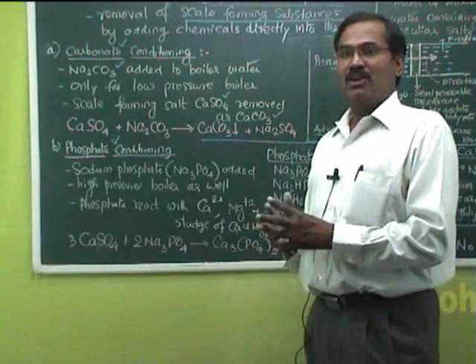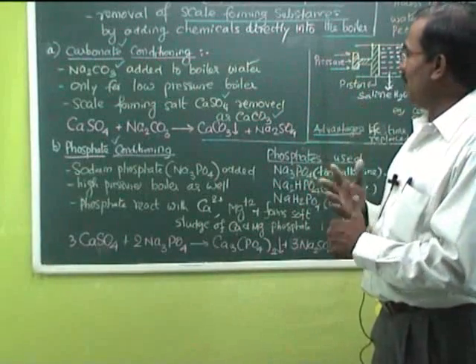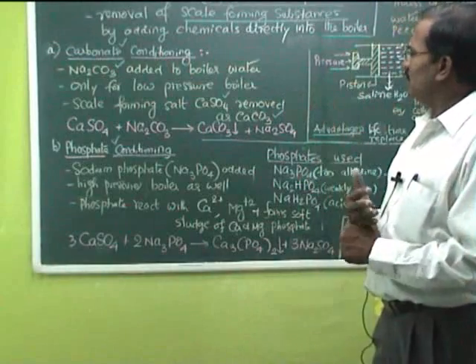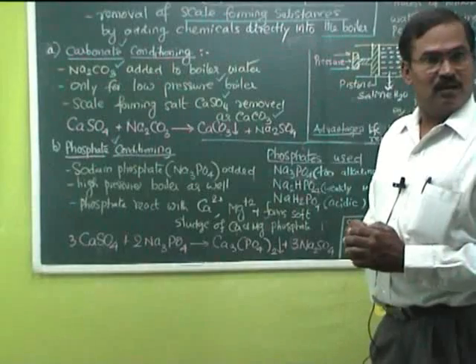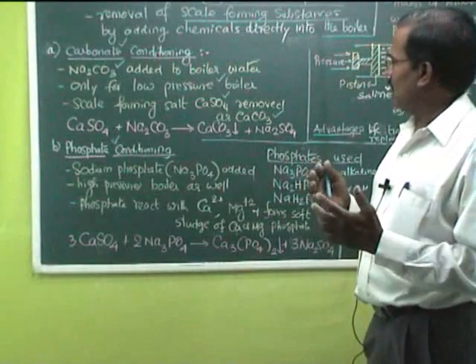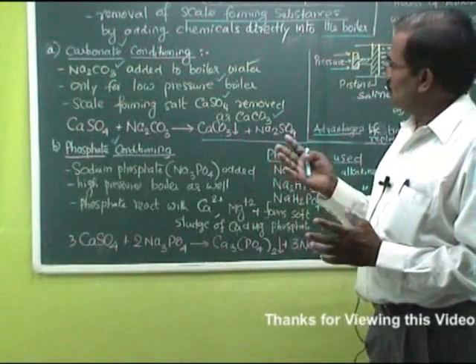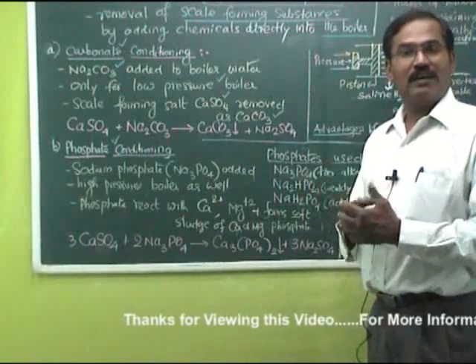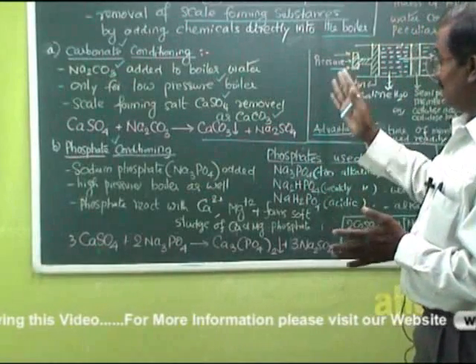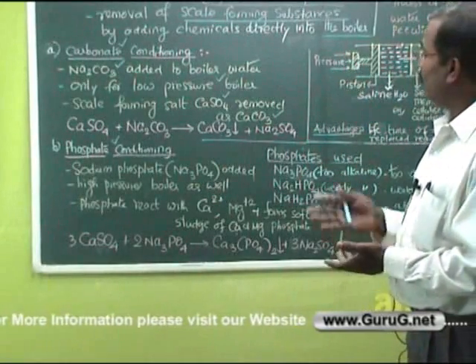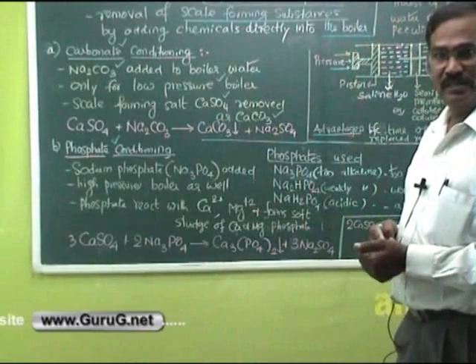Calcium carbonate can be removed readily because it is a water-insoluble precipitate. In carbonate conditioning, we are adding sodium carbonate, and this is mainly applicable for low-pressure boilers. This cannot be used for high-pressure boilers because in high-pressure boilers, sodium carbonate undergoes hydrolysis to give sodium hydroxide, which leads to caustic embrittlement. So this is applicable only for low-pressure boilers.